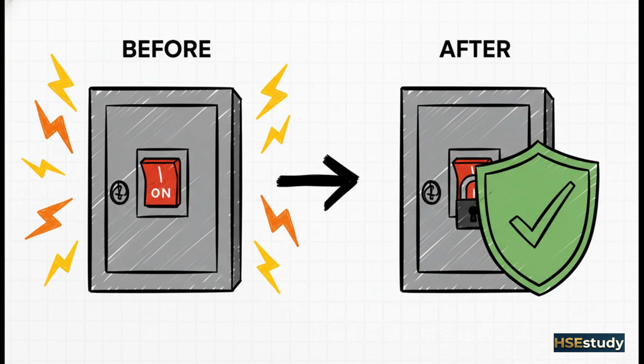This is the heart of NFPA 70E. The number one goal is to create an electrically safe work condition. That means de-energize the equipment, turn it off, lock it out, test it to be sure. The only way to completely eliminate the hazard is to make sure the power is off before you start the work.